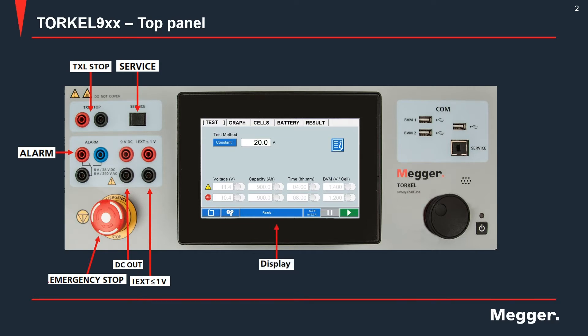The TORKEL unit has a seven-inch touchscreen display. There are a couple of USB ports provided for BVM connections. There is a third USB port provided to insert a USB stick for data transfer to and from the instrument, or if you want to use a USB mouse. There is also an Ethernet port provided, again marked service.